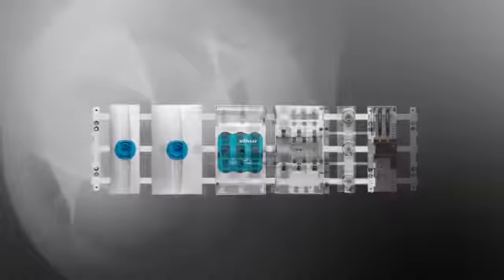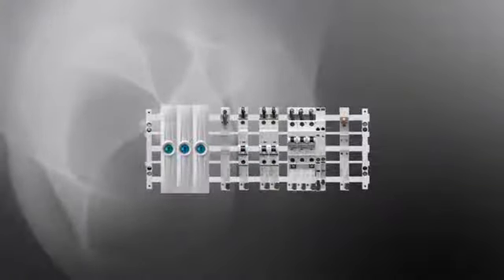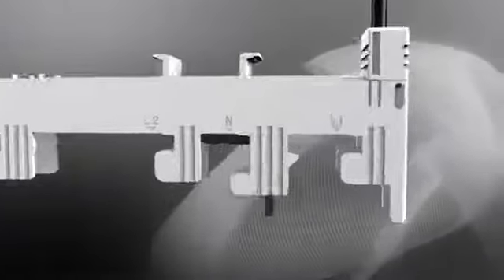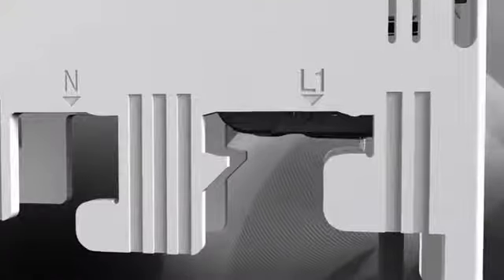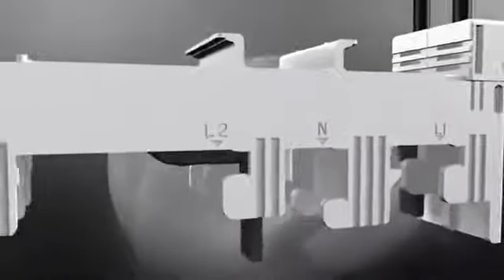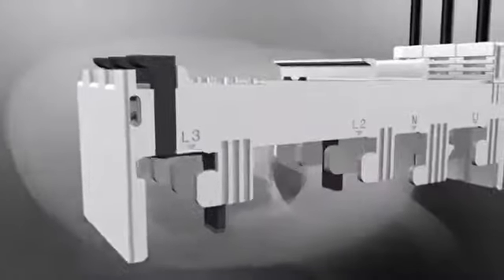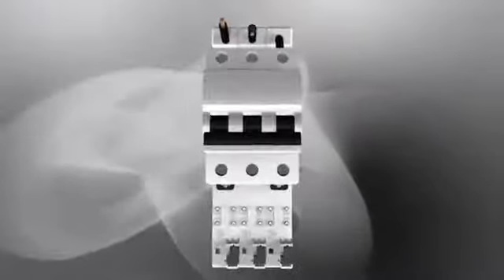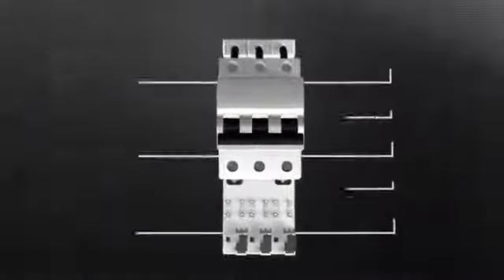The 60mm system compact comes as a 4-pole and 5-pole version for building automation. These versions have been specially developed for use with circuit breakers. The basis for all solutions is the single-pole 18mm modular bus bar adapter with an adjustable connection foot. This foot visibly engages at the selected position. The adjustable foot can be freely selected for the 3 outgoing cables, L1, L2, L3, as well as N. This means that one product can handle all the tasks that crop up during installation. A 4-pole or 5-pole system can, of course, also be combined with a 3-pole system.